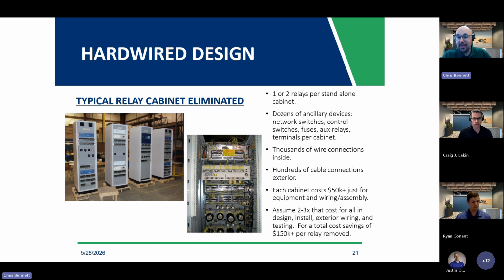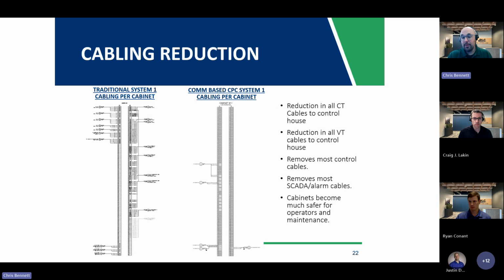You see in the picture on the right that those are the thousands of connections that we're talking about. Each one of those little SIS wire jumpers needs to be placed, labeled, tested. Takes time, takes money. We estimate each cabinet typically costs about $50,000 just for the equipment and the wiring assembly. And when you factor all that in for who designed it, actually installing it, testing it in the field, ringing everything out, you're looking at probably about $150,000 or more per relay removed from the scheme. So definitely some big benefits there.